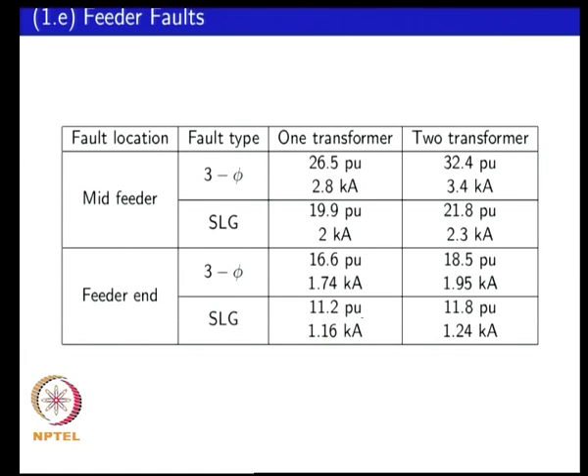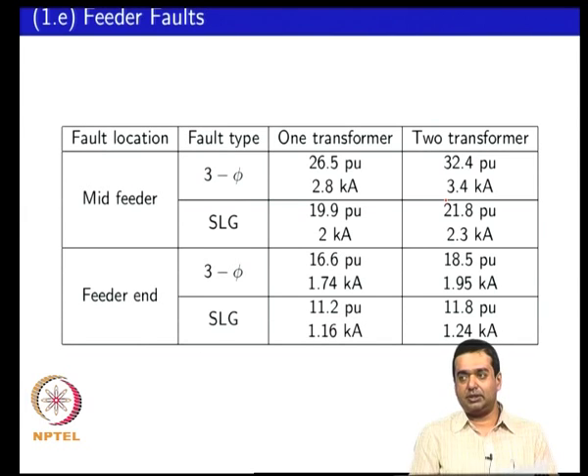You can see that there can be a change in fault current levels depending on whether there are two transformers or one transformer at the substation. Your protection devices should be able to handle a possible range of current levels — not just for single line-to-ground and three-phase faults, but for situations involving switching of transformers or switching of lines which can occur on the system.